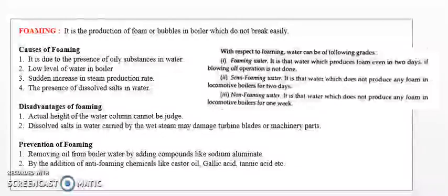Now, foaming. Boiler water carryover is the contamination of steam with boiler water solids. Bubbles or froth actually build up on the surface of the boiler water and pass out with the steam. This is called foaming, and it is caused by a high concentration of any solids in the boiler water. Foaming tendencies are increased with the increase in alkalinity and solids content. Stable foam bubbles contain boiler solids and are carried forward with the steam, giving rise to carryover.